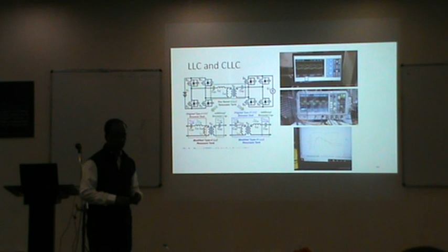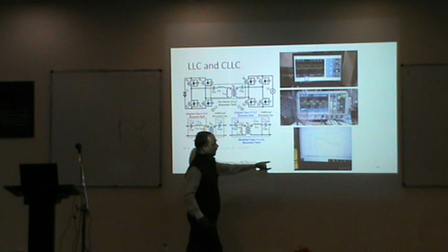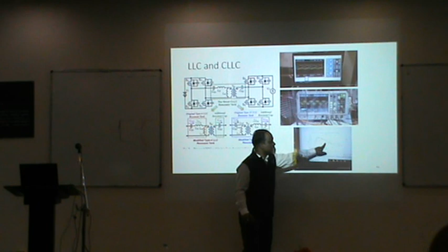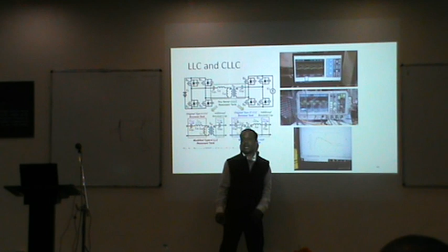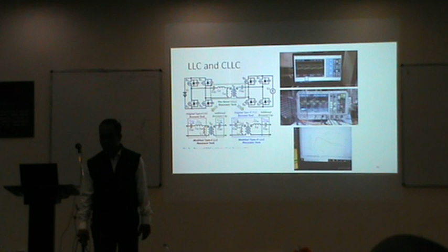If you operate at lower load, core loss will increase. Lower voltage or lower load means core loss increases. So to optimize those two parameters, we operate the transformer where it gives maximum efficiency. These are real tested results, and they show maximum efficiency at 80% of load. Beyond that, you should not go, otherwise efficiency reduces.